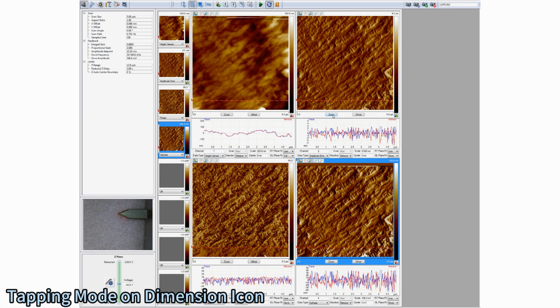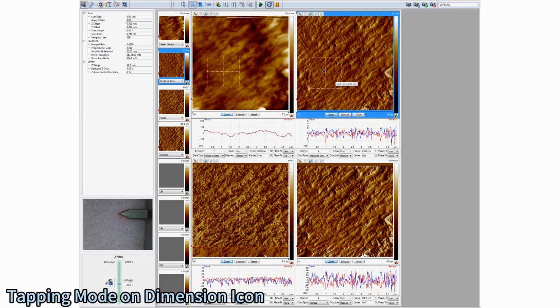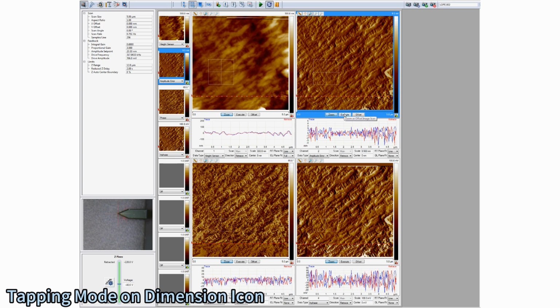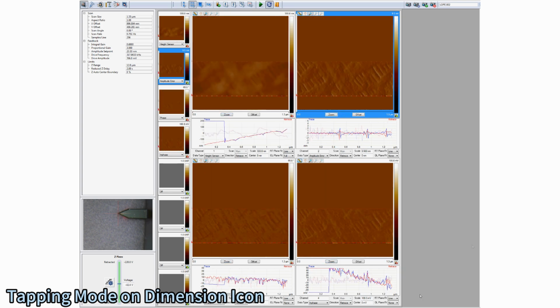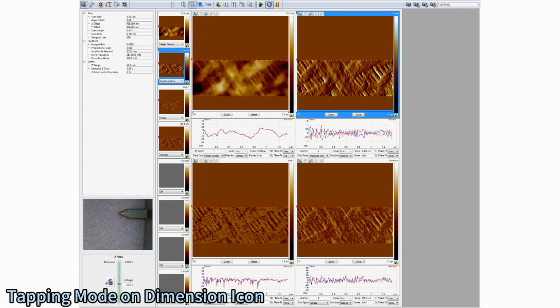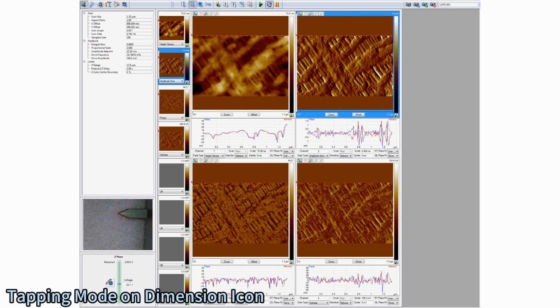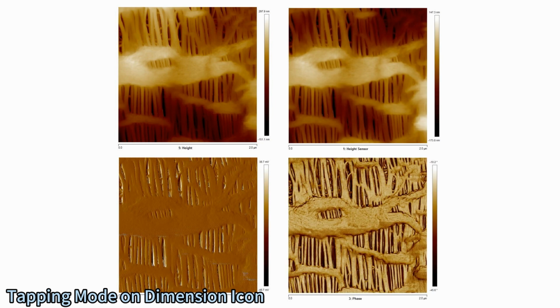If a specific area of the sample is of interest, the user can activate the Zoom button to select that region. Click the Execute button to begin scanning within the newly defined area. While the scan is collecting, the user may choose to adjust parameters such as speed, gain, or set point if improvements in the image are necessary. Allow the scan to complete and save the images if they are satisfactory. The results of a multi-channel tapping scan can provide useful and revealing information.